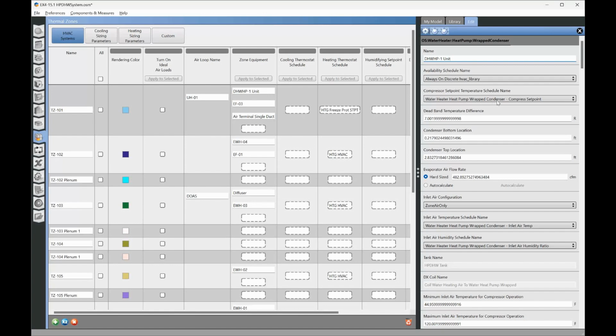Compressor set point temperature, that's the temperature set point of the compressor, the temperature of the water that we want to produce and keep inside the tank. And then we have a dead band of about 7 degrees. So 7 degrees below this temperature, that's when the compressor kicks on. The compressor heats up the tank this additional 7 degrees, and then the compressor kicks off at this compressor set point temperature.